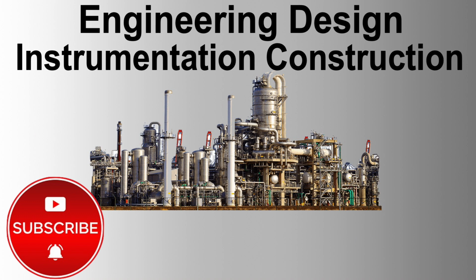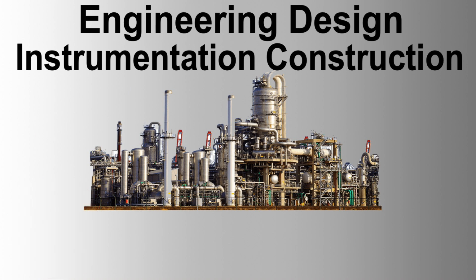Locations of the instrument stands, marshalling boxes, etc., shown on layout drawings are approximate. Contractor shall be responsible for final location of the instruments, considering all relevant installation requirements of this specification. The overall availability and reliability of the instrument installation shall be demonstrated by the contractor. Unless otherwise stated, the construction design life shall be 30 years, with an uninterrupted period of operation of 3 years.